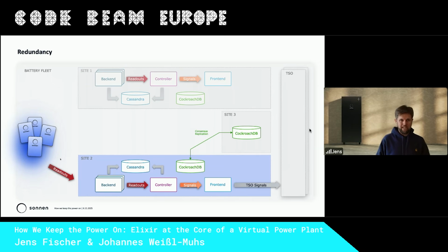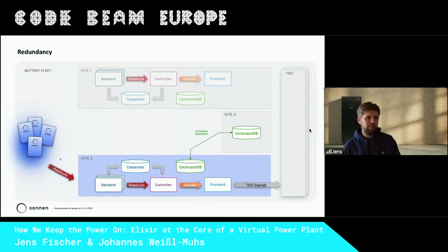They don't change. They don't have to migrate. We can still continue immediately steering them. And it's good for overhead in the number of batteries. If the frequency deviation is not too much, we don't need all the batteries. And within around 30, 40, 56 seconds, we have a complete switchover and a healthy system again.